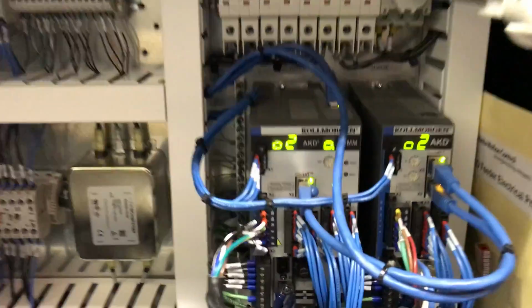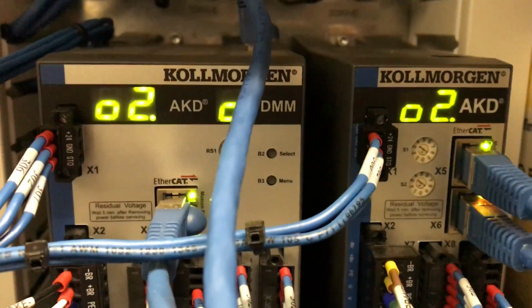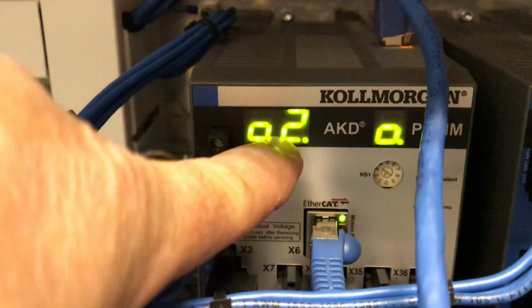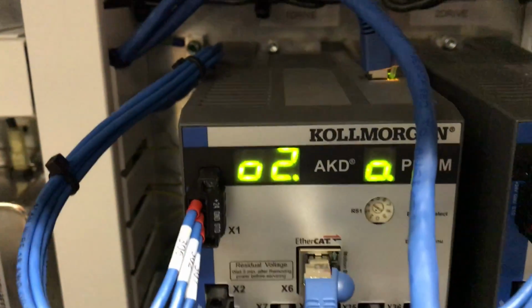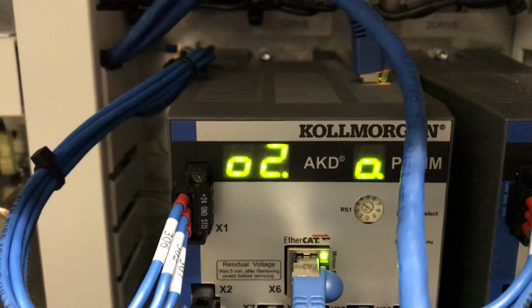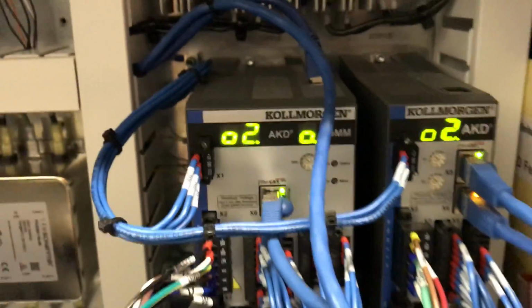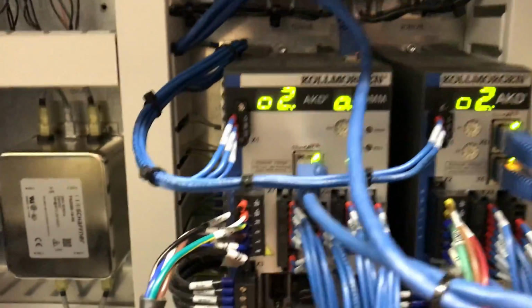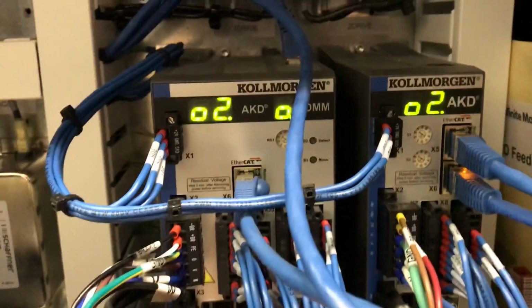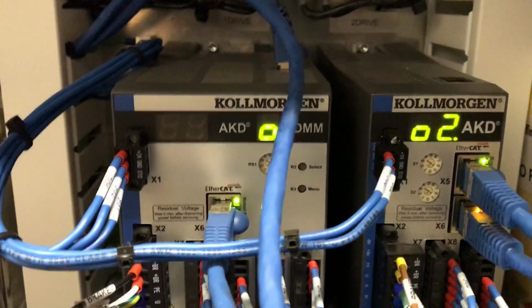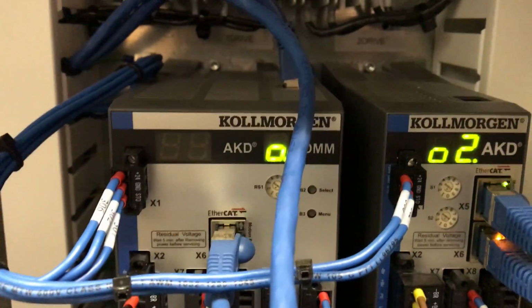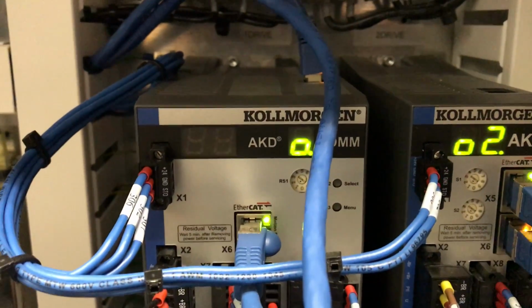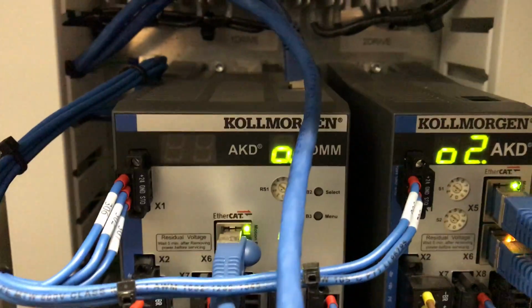Reset the fault. When we go back to O2, that means these drives can be operated. Now, a number of faults can be displayed in this window, and these faults can be looked up in a book, which I'll show you in a second. But I'm going to create a fault right now by unplugging the servo motor encoder cable. I'm unplugging it, and now we see that we have on the horizontal drive a fault 415, F415.